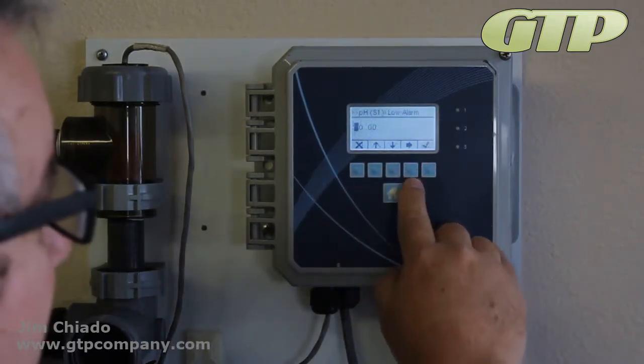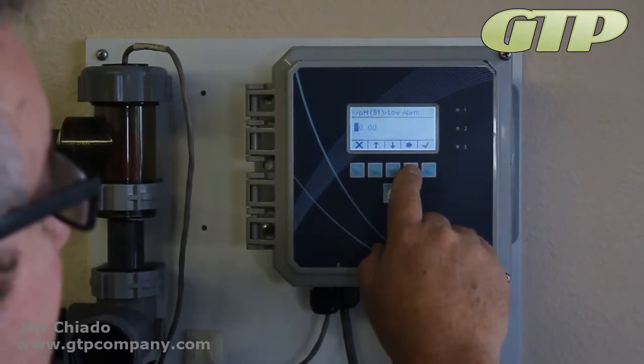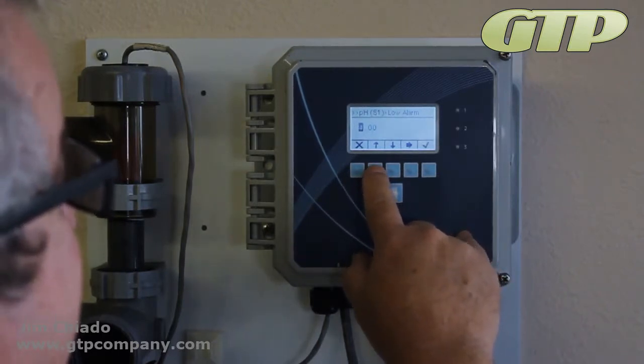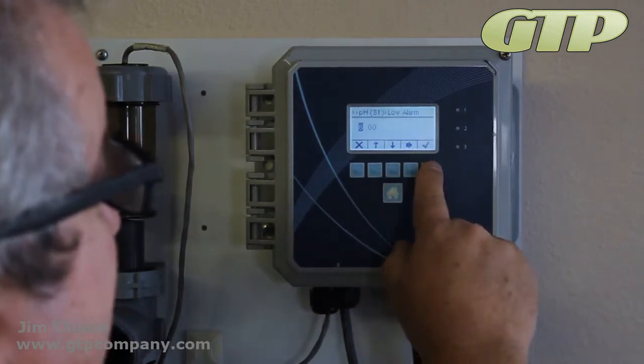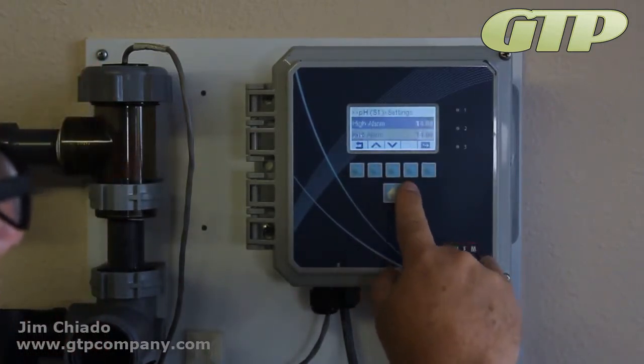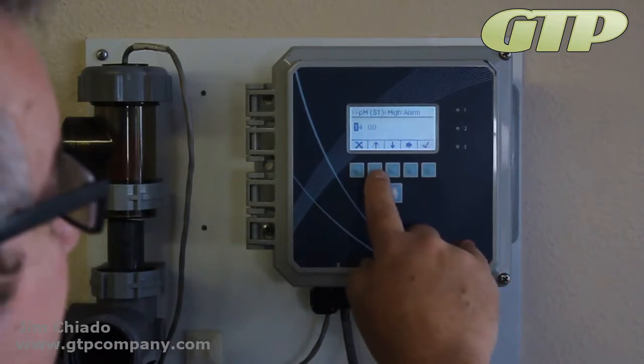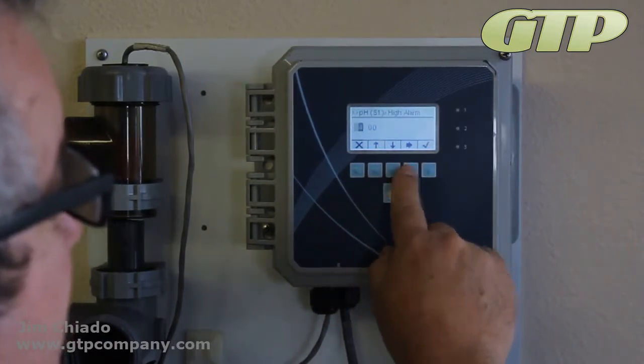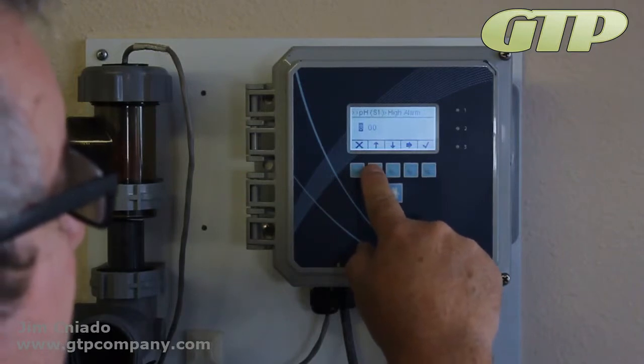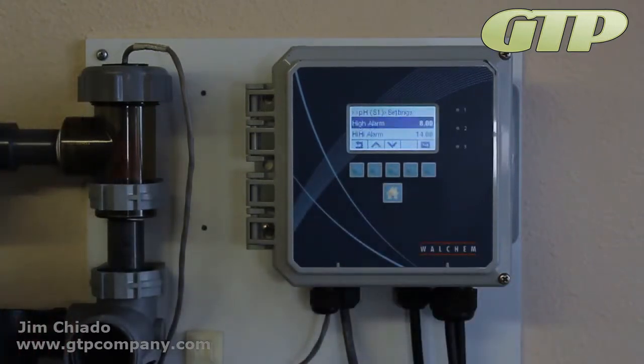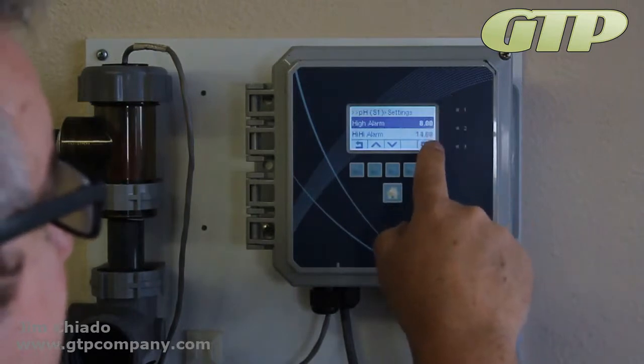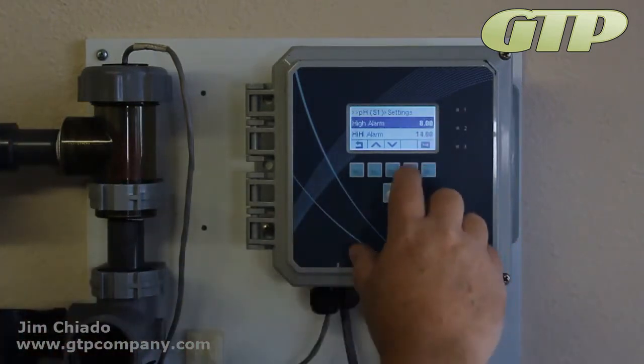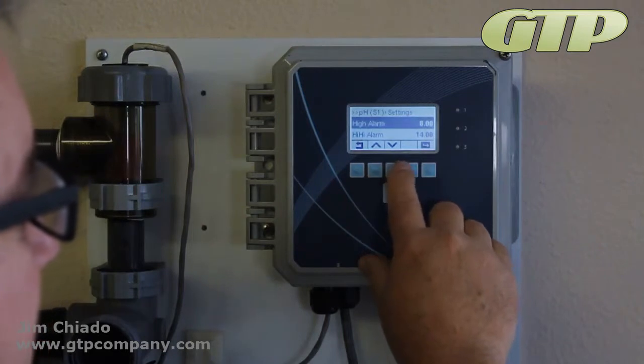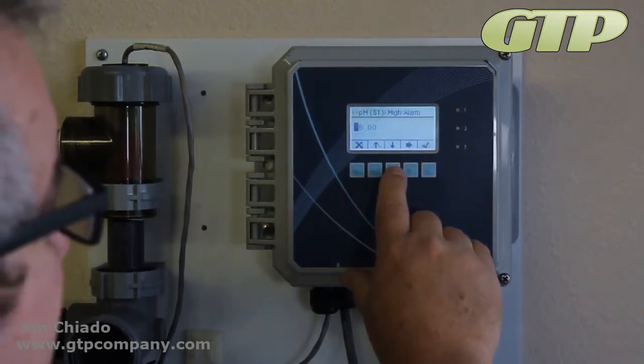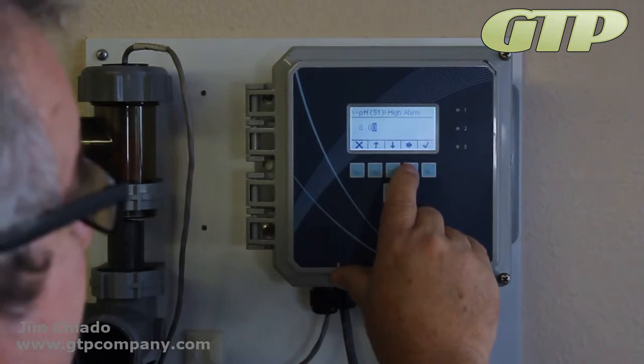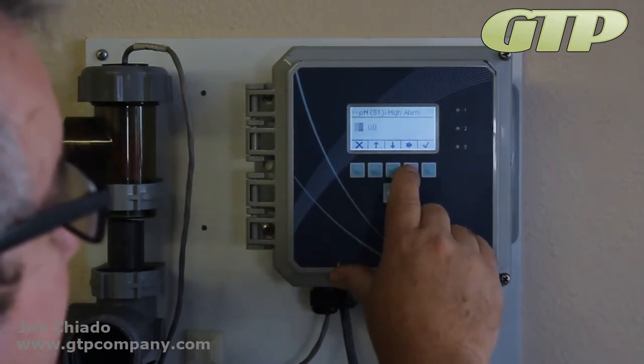In here we're going to go to low alarm. We're going to set the low alarm at 5. Let's make it 6. And we're going to go ahead and set the high alarm, and we want to go to 0. And we're going to set it to 8. Okay, and that's just to give us an alarm at the top. Matter of fact, we're going to set it a little bit higher than 8 because it thinks this thing is 8.14. Remember, we saw that on the first thing. So we're going to change that to maybe 8.5. See how it went back around?